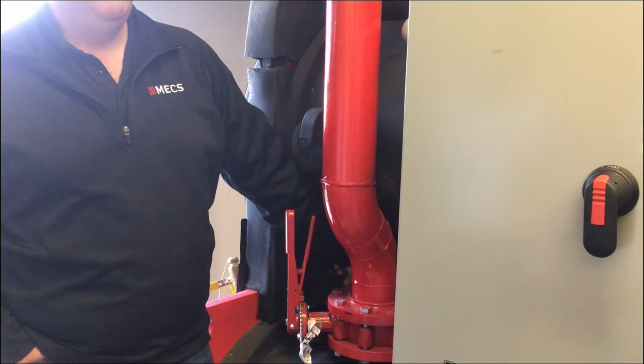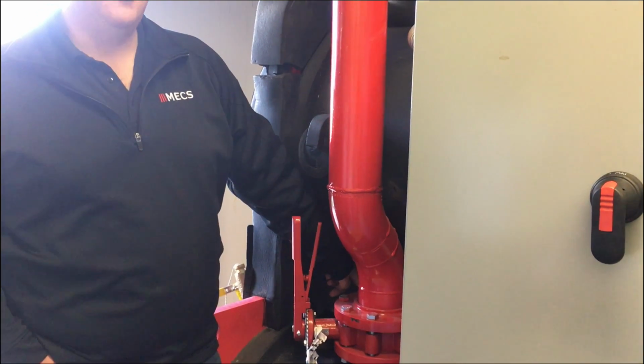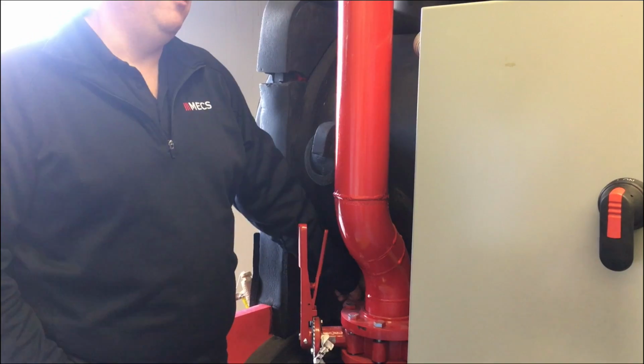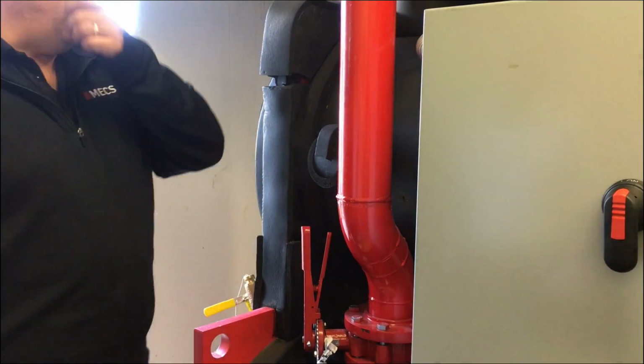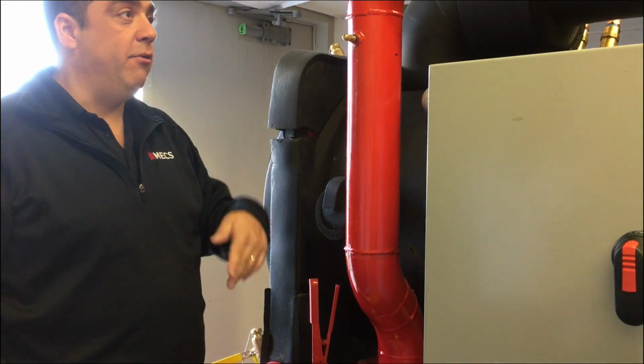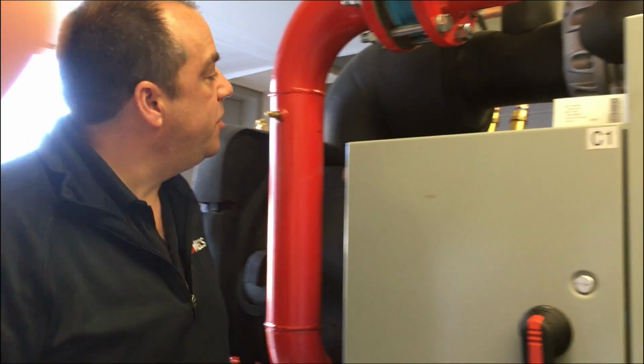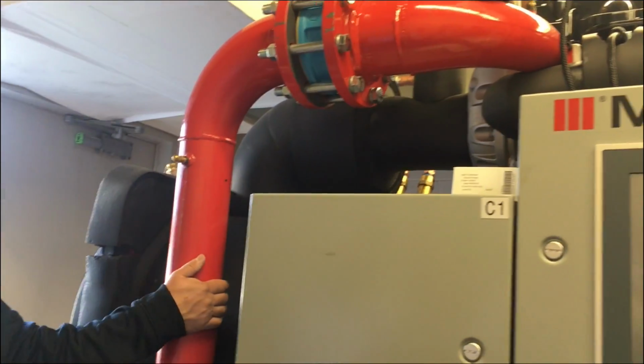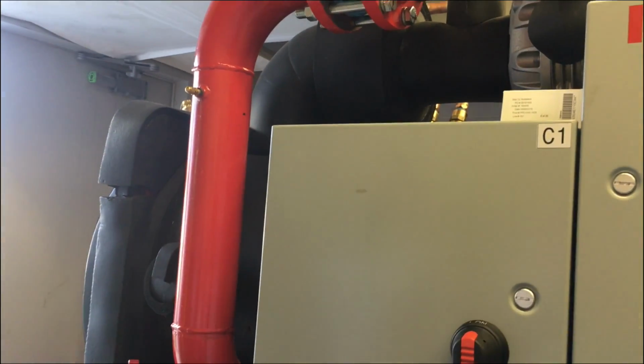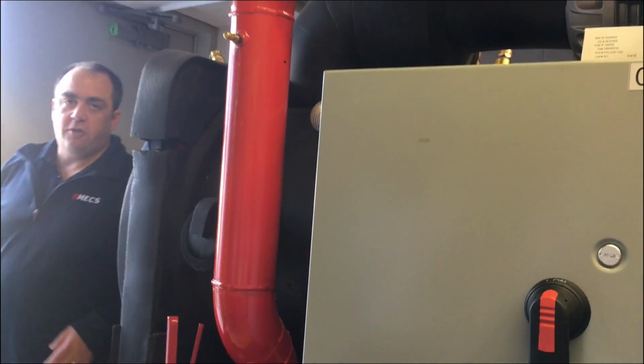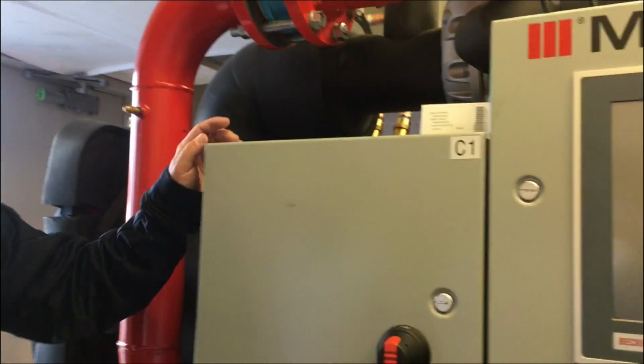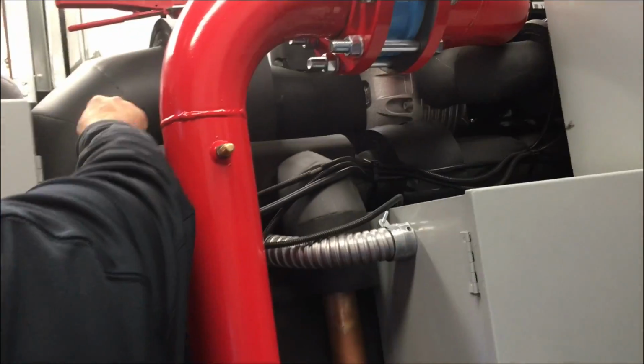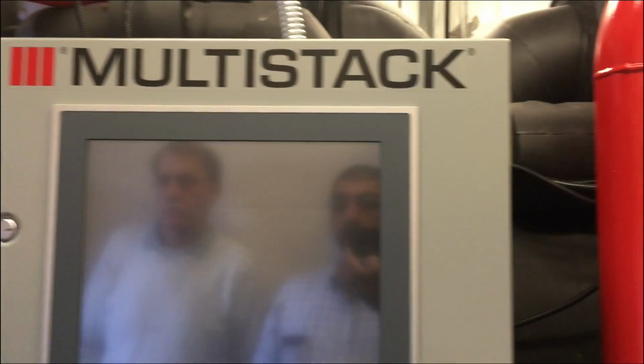If we lose flow and then you regain flow, it's going to start up if it's being called for. You don't have to come in here and hit your resets or clear a button. Same thing with low pressure or standard high pressure. The low pressure switch is on the other one. So there's one low pressure screw-in switch right on the back side of this that we'll point at. That one has a Schrader behind it because it's not nearly as critical as the high pressure.